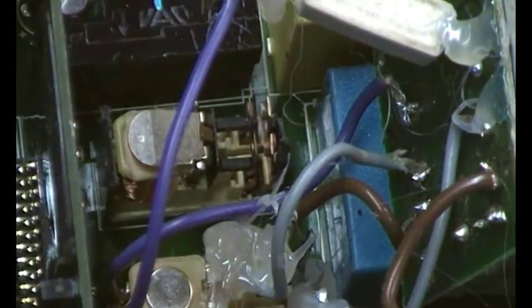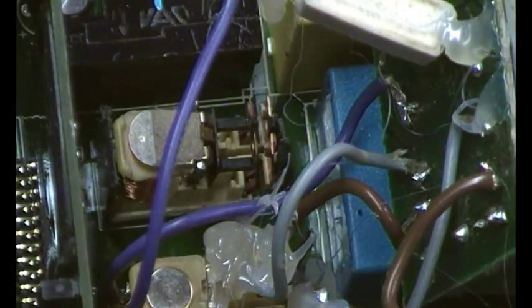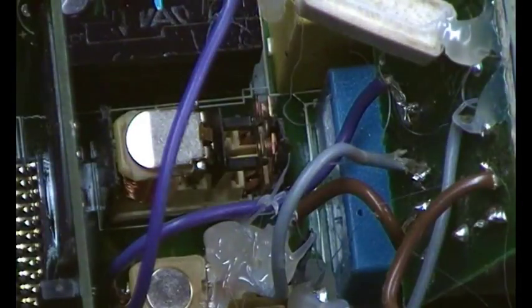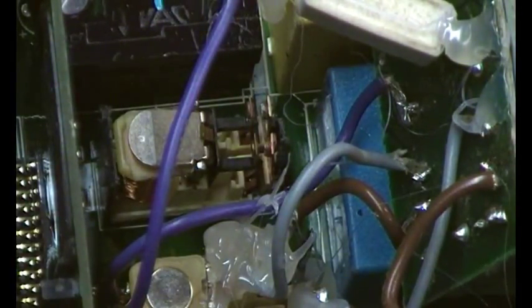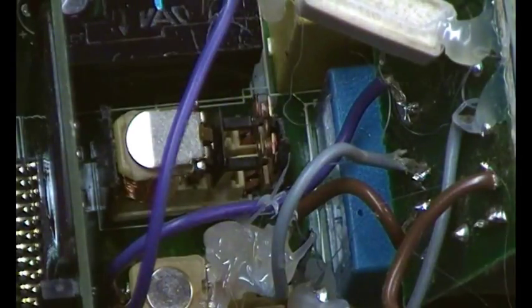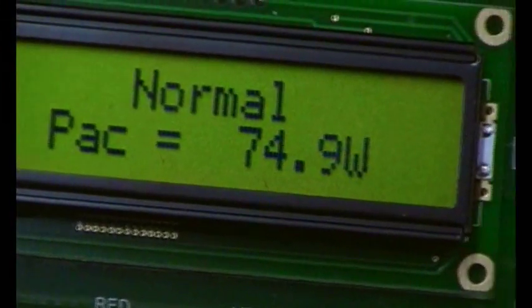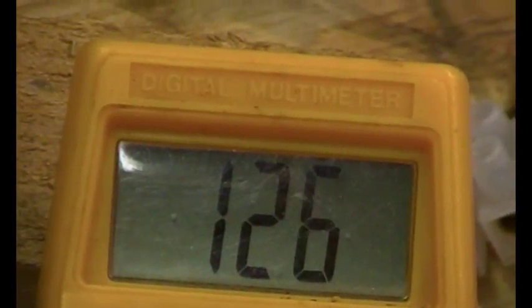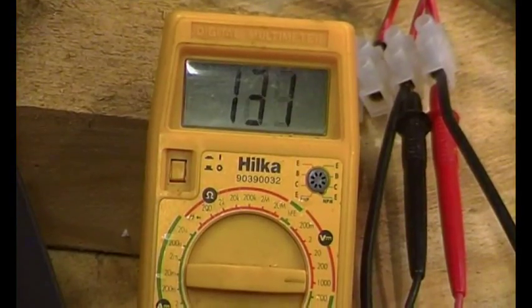So this is a view of one of the output relays with the top off, and we're down to four seconds now, two, one, go. And it's running, so they switch on and off and on and off. And now it's running, let's just come down to this. There we go. And we started off at 200 volts, and now there's a load on it - where's the - there we go, it's 126 volts, which is a bit low, need to keep it up a bit.